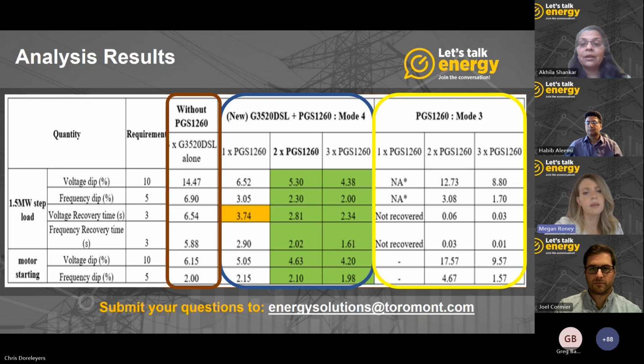Great, thanks, Akhila. Can we expect that we would have the same results across all natural gas generators? No, Megan. The results will not be similar across the board for all natural gas genset ratings. The sizing and the stability calculations have to be done on a case-by-case basis. The different models and the different ratings of the generator sets have different transient performance.